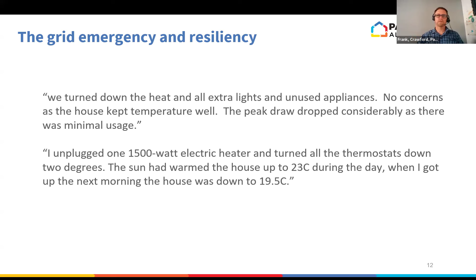These last two quotes are from passive houses, really showing what a passive house building envelope can do. The first one wasn't even fully built - it was under construction, with the envelope about 95% complete. No mechanicals were operating, no one was living in it, no internal heat gains. They heated the house with a single 4,800 watt electric resistance heater, which is actually less than the heating design load of about 5.5 kilowatts for this house. That heater maintained the temperature overnight, and when the sun rose the interior temperature rose too. The house basically didn't care what the weather was outside - it maintained its temperature with a very small electric resistance heater.